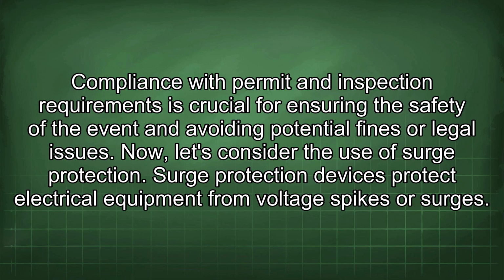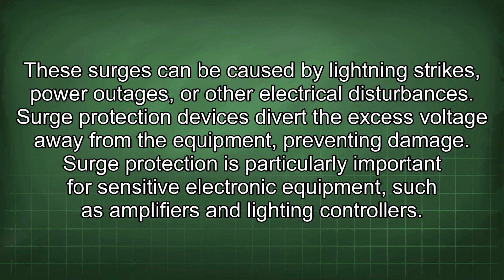Now, let's consider the use of surge protection. Surge protection devices protect electrical equipment from voltage spikes or surges. These surges can be caused by lightning strikes, power outages, or other electrical disturbances. Surge protection devices divert the excess voltage away from the equipment, preventing damage. Surge protection is particularly important for sensitive electronic equipment, such as amplifiers and lighting controllers.